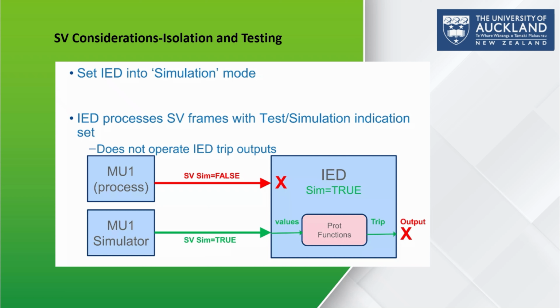When the IED is set to sim true, it will ignore all sample value frames that come from the real process, because those frames are not marked as simulation. In other words, the IED blocks any data with SVSIM false. At the same time, it accepts only the SV frames with SVSIM true coming from the simulator. This ensures that during the testing procedures, only the simulated test values influence the relay's internal protection functions, right?